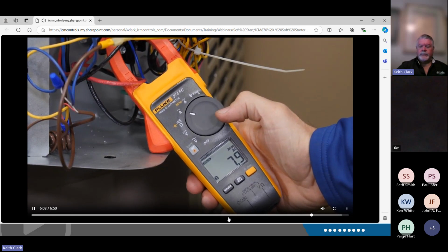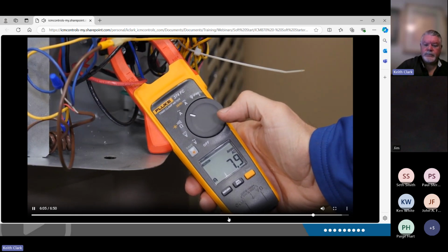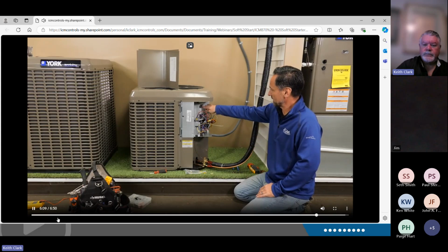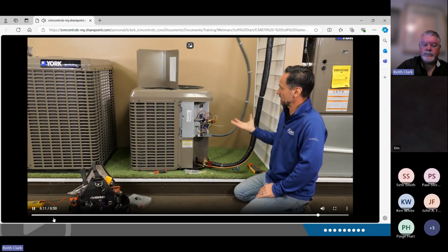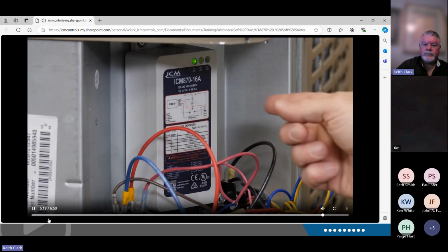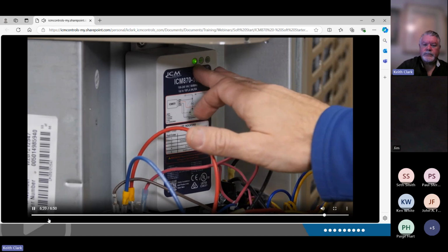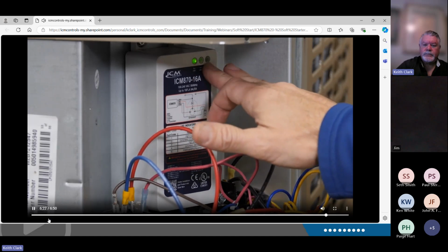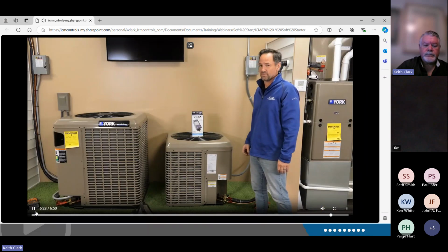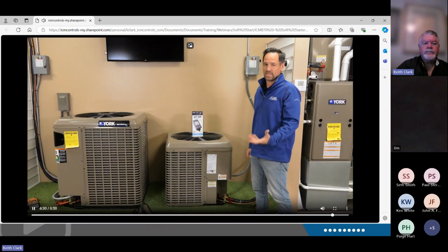7.9. And if you remember, our previous reading was 52. Okay, now that we're up and running, we're going to have a green light here. It's going to go through its learning algorithms to learn the start requirements of this condenser. If there are any fault codes or any issues with the unit, you'll see there's 2 other LEDs here that will flash according to the fault code in the owner's manual. And that completes another successful installation of one of our ICM products. As always, thank you for watching.